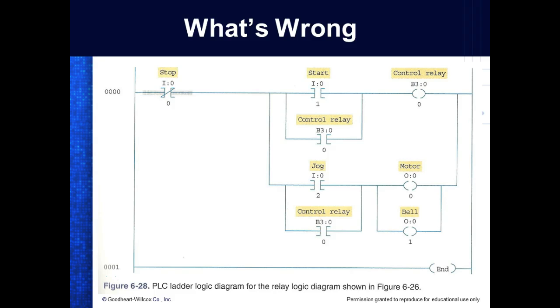That's the address. That's input 0, bit 0. What Allen Bradley does, RSLogix doesn't do this, but Allen Bradley comes up here and puts the word number, and then it puts the bit under that. So this is input, word 0, or port 0, bit 0. So this right here means nothing, that's the address. You can see every one of them do the same thing over here when they're using all these bit files.